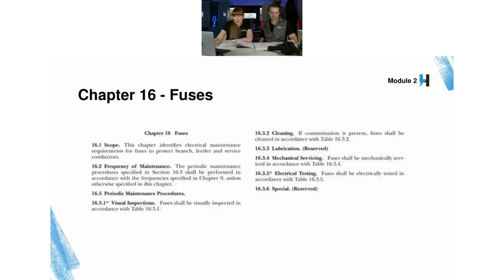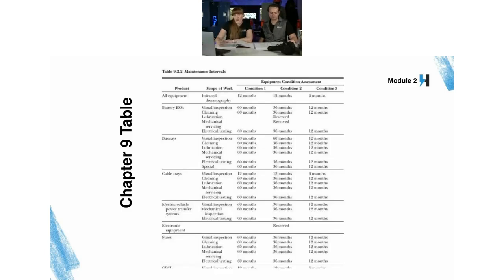So what does that mean? Well, now this becomes an every-year task that you're checking on. If you check on it, maintain it, and improve the condition, that's okay—there are guidelines for modifying how often you have to do this. So if you have a condition 3 piece of equipment, like this fuse set, and you perform maintenance and visual inspections for some period, and it's now condition 1 because you've really revamped it, you can make that determination, and that's also detailed in chapter 9.